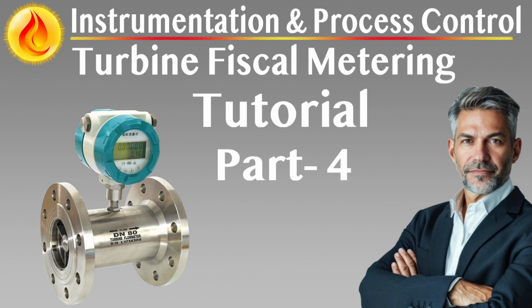The prover must be designed as a mechanical displacement type, either unidirectional or bidirectional. Bidirectional provers are typically preferred for their compact footprint and balanced pressure dynamics, especially in offshore or space-constrained environments.